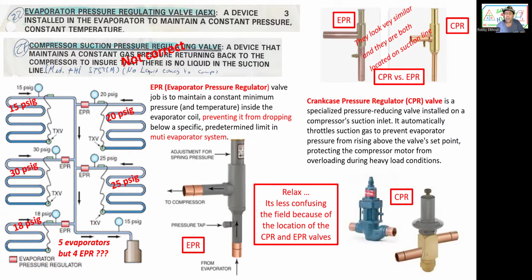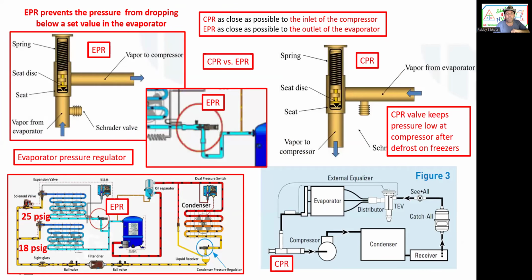The CPR is a specialized pressure reducing valve installed on the compressor's suction inlet, automatically throttling suction gas to prevent pressure from rising above a set point, protecting the compressor from overloading during heavy load conditions. So we have a walk-in freezer or any freezer. Temperature is usually 0 degrees in the freezer. Evaporation temperature is -10, but defrost temperature is 40. After defrost, temperature is 40. The pressure goes up like crazy for the compressor. There goes your amperage, past the rated RLA, the rated load amps. The compressor will overload. So we need the CPR to prevent the compressor from overloading.